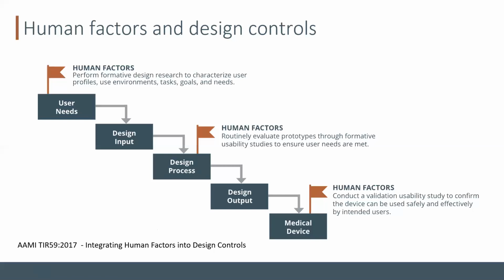And you had described that the company should be identifying early on what some of those critical tasks are and designing some possible screening tests to figure out which design form factors might work well for usability and which might not, early on, with some low fidelity breadboard designs or something you clamp onto the table with a C clamp, something a little bit more crude. Work it out during the early design process before you finalize your outputs, before you've done any verification and validation testing. So it's really part of that formative testing.